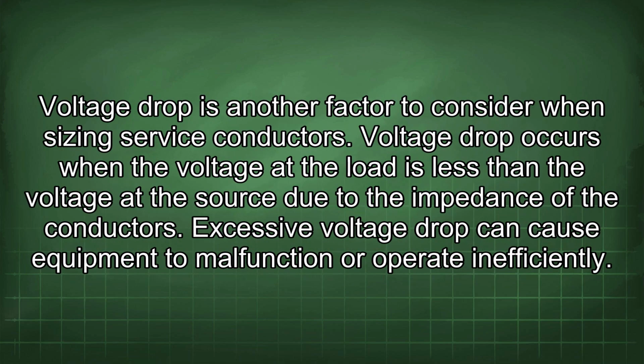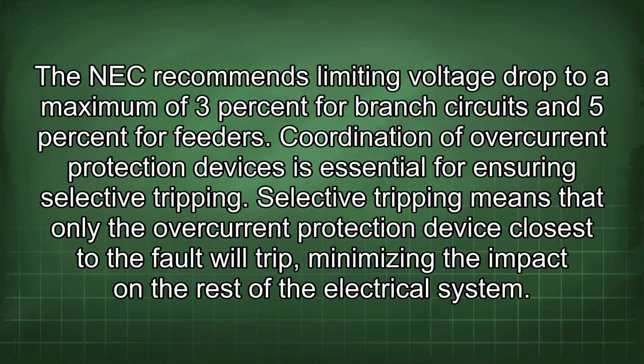Voltage drop is another factor to consider when sizing service conductors. Voltage drop occurs when the voltage at the load is less than the voltage at the source due to the impedance of the conductors. Excessive voltage drop can cause equipment to malfunction or operate inefficiently. The NEC recommends limiting voltage drop to a maximum of 3% for branch circuits and 5% for feeders.